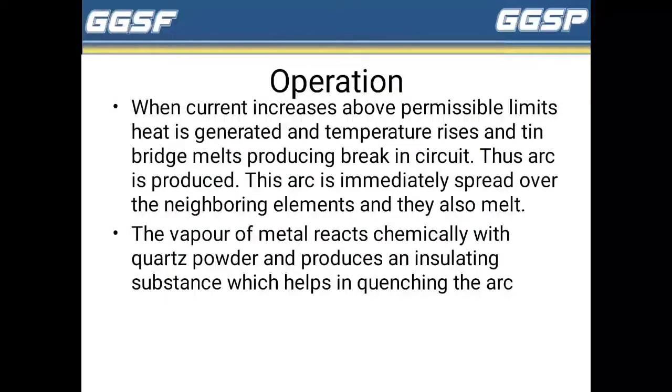Due to melting of the fuse element, the arc is produced. This arc immediately spreads over the neighboring elements and they are also melted. The vapor of the metal reacts chemically with the quartz powder and produces an insulating substance which helps in quenching of the arc.